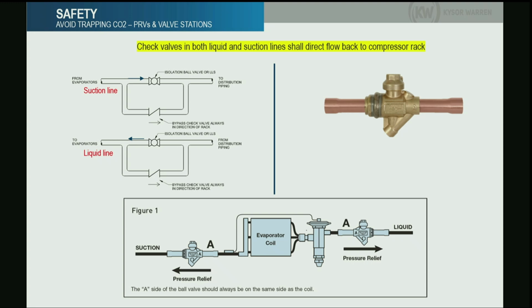Yeah, I've been hearing rumors that they're saying these valves are not able to pull proper vacuums inside the cases from the rack, and that they've had to go into the case to pull a vacuum. No, it shouldn't be the case. We have that installed in many, many stores and no problems. Okay.